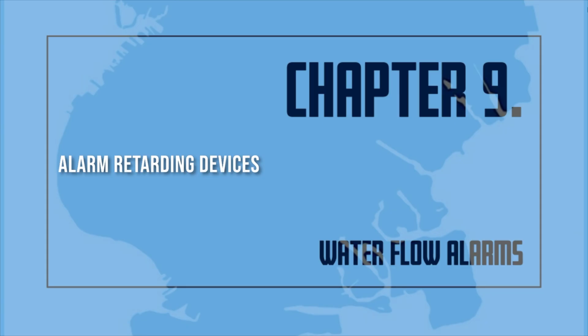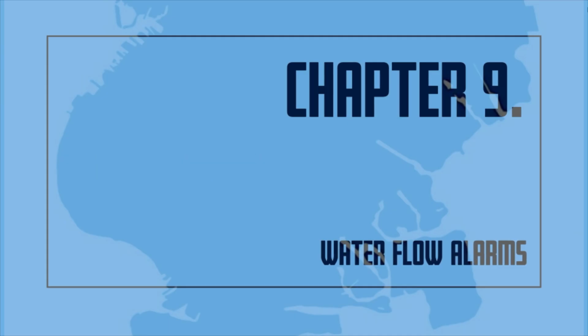Alarm retarding devices. An alarm check valve that is exposed to changing water supply pressure needs an alarm retarding device. This is required to prevent false alarms when the check valve clapper is lifted from its seat by a temporary pressure surge. Vane-type water flow switches' sensitivity can also be adjusted to changing water pressures.